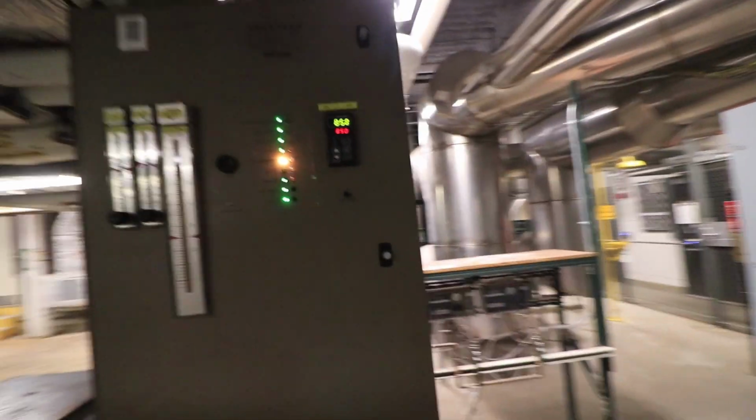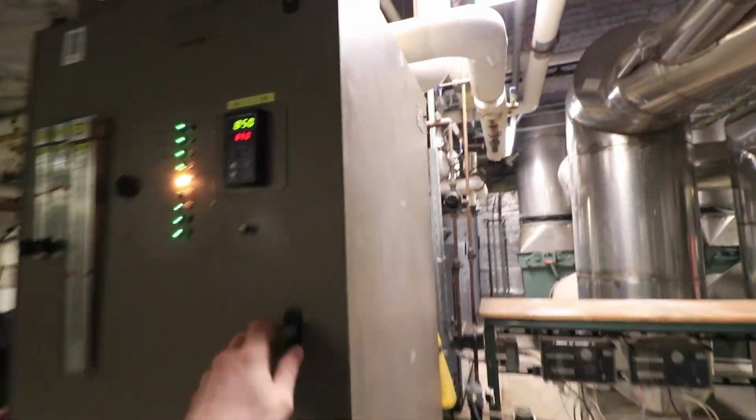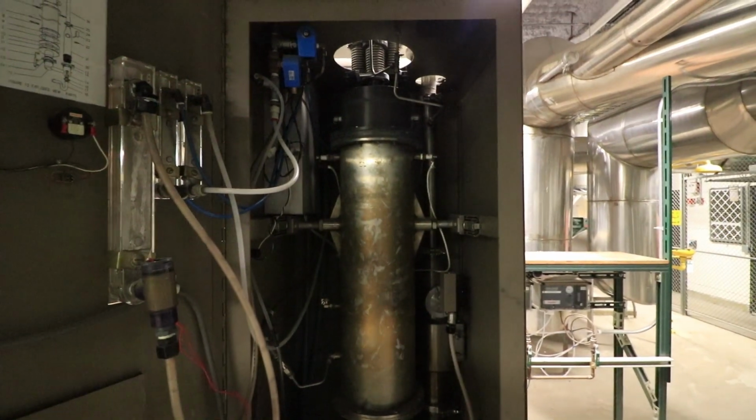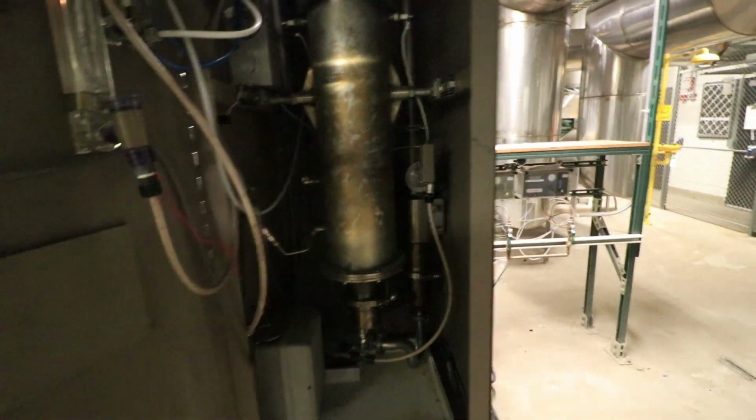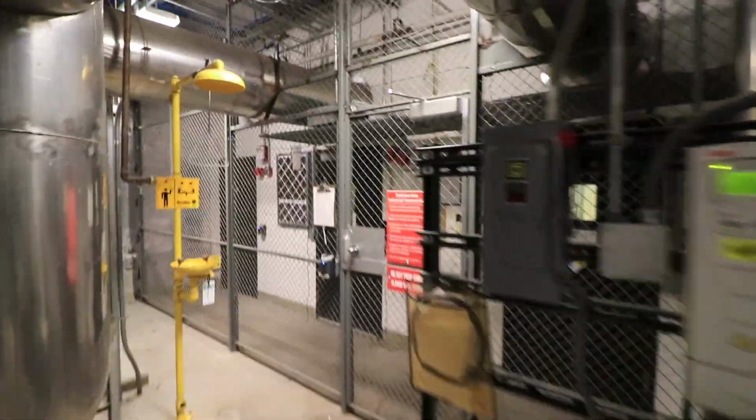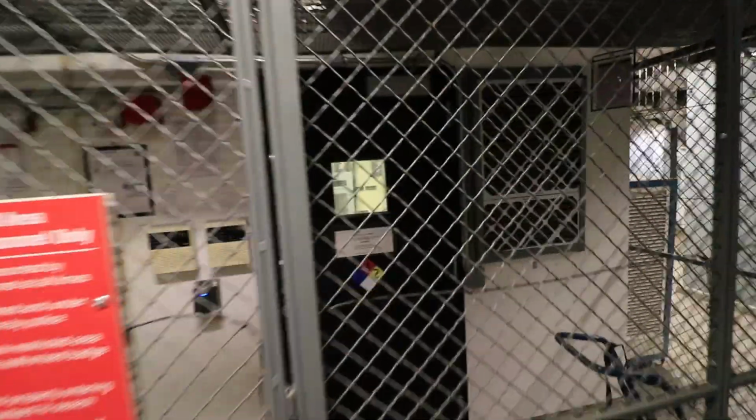The toxic gas scrubber burns all of the effluent from the MOCVD and the gas source MBE reactor in order to render it inert prior to ejecting it from the roof of the building via the scrubber exhaust fan shown previously. Toxic gases are stored in a secure vault in the penthouse. We have a number of toxic gases that are rather hazardous, and all of these are stored in this ventilated space in the penthouse and then delivered downstairs through coaxial double wall lines.